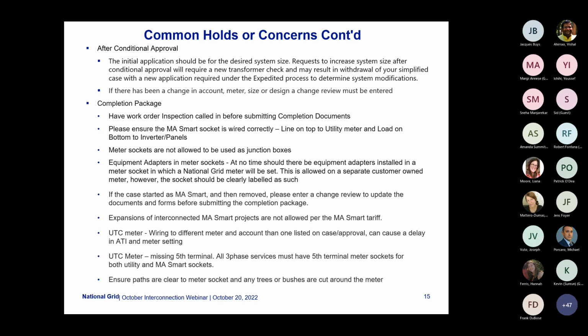Ensure that the Mass Smart socket for Mass Smart systems is wired correctly, with line on top and load on bottom — it should always be wired this way. Meter sockets are not allowed to be used as junction boxes, and equipment adapters in meter sockets are not allowed. At no time should there be an equipment adapter installed in a meter socket where a National Grid meter will be set. You could use them, but only on a customer-owned socket, and it has to be labeled as such.